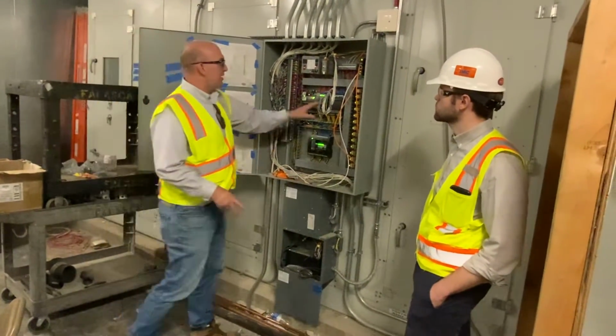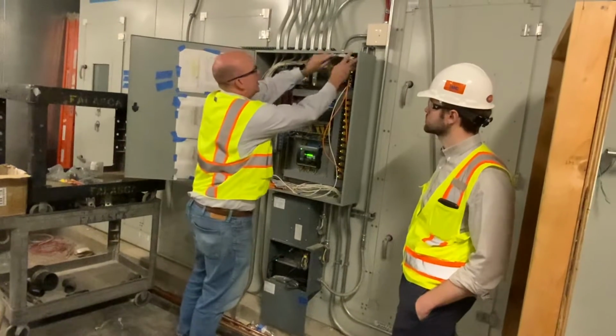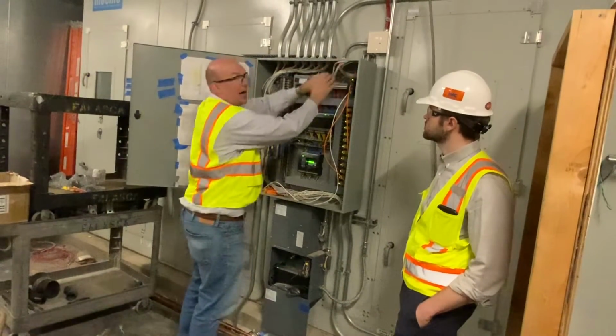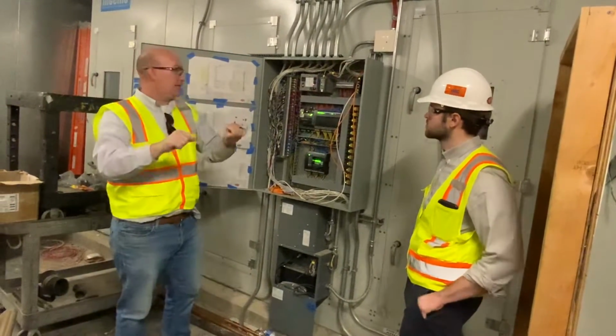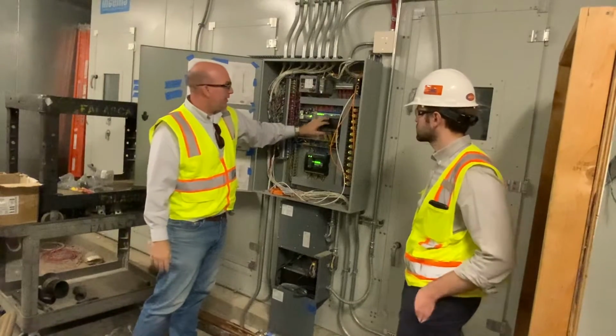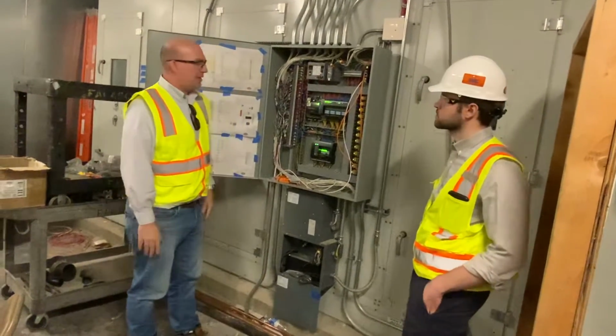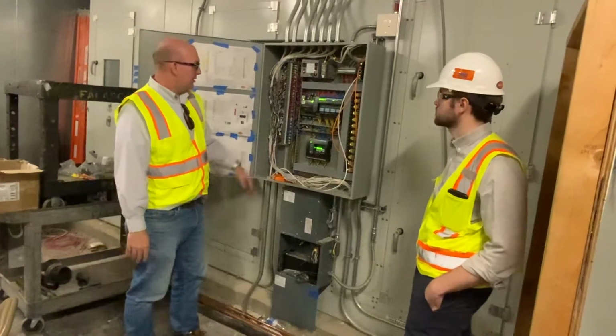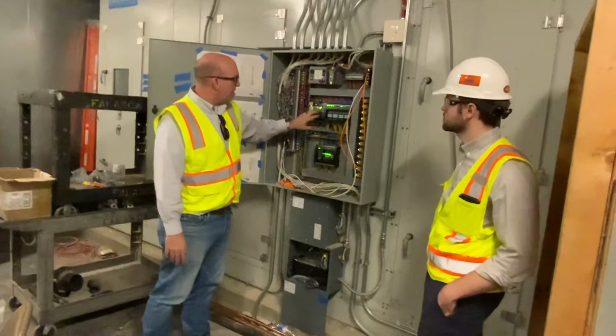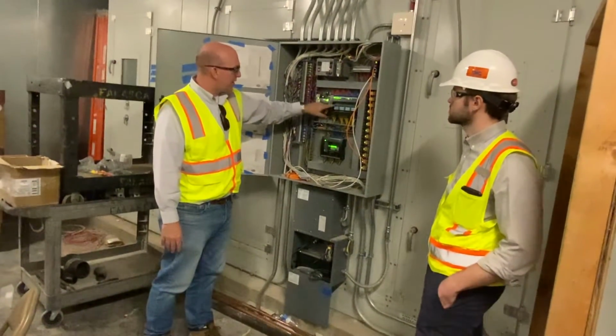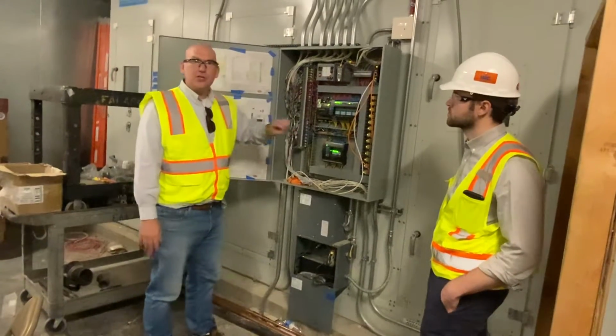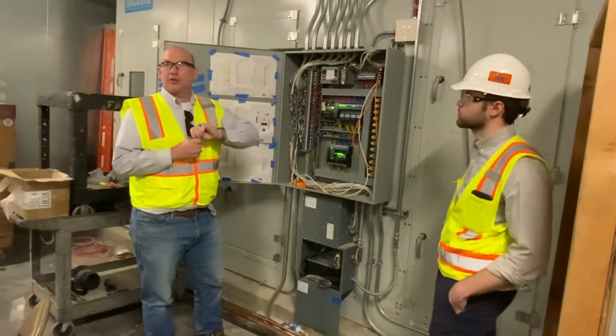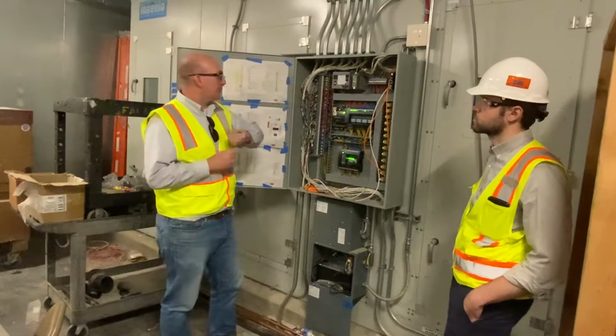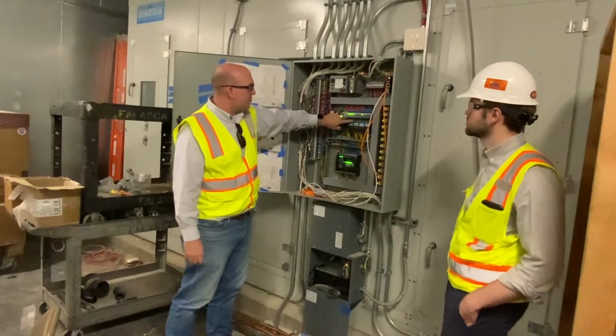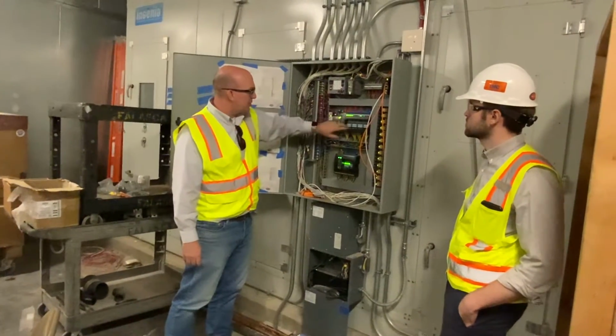The controllers themselves, if you're familiar with the older line, would have had pots and switches and whatnot next to the connections. All the same thing here, just underneath this cover. All of these upper level OF controllers are going to have hand-off-auto switches. So if you did want to manually trigger a relay, manually do something right from the controller, you can do so with these switches here, and they line up to the outputs that you see above it.